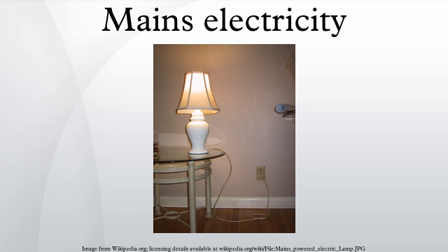Electrical appliances are used extensively in homes in both 230 V and 120 V system countries. National electrical codes prescribe wiring methods intended to minimize the risk of electric shock and fire. Many areas such as the USA, which use 120 V, make use of three-wire, single-phase 240 V systems to supply large appliances. In this system a 240 V supply comes with a center tap neutral to give two 120 V supplies, which can also supply 240 V to loads connected between the two line wires.